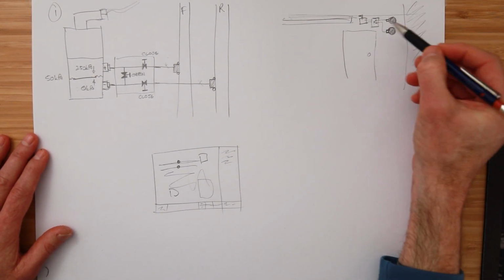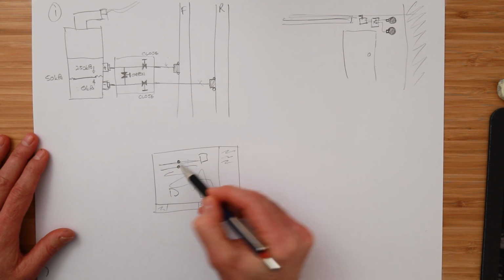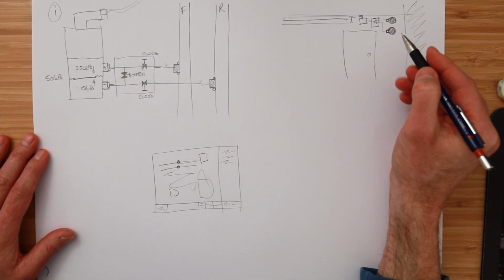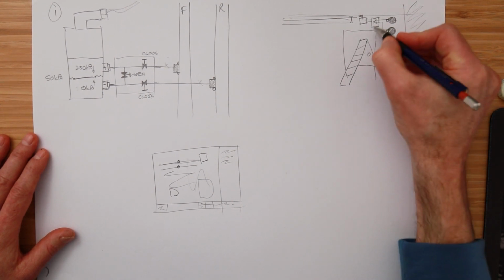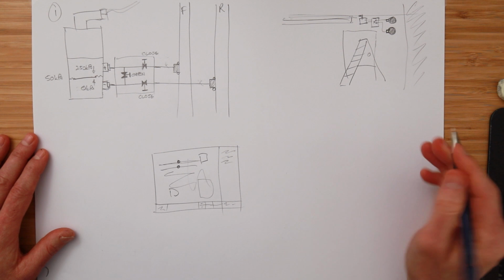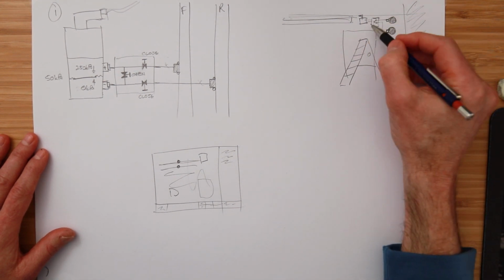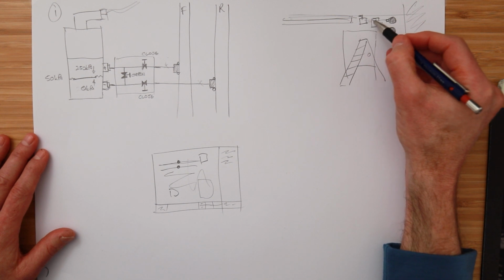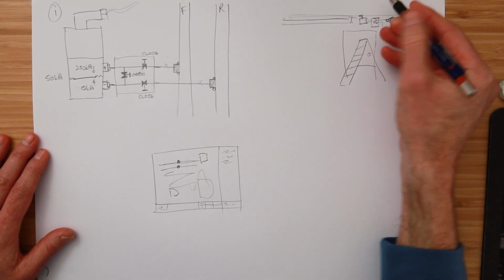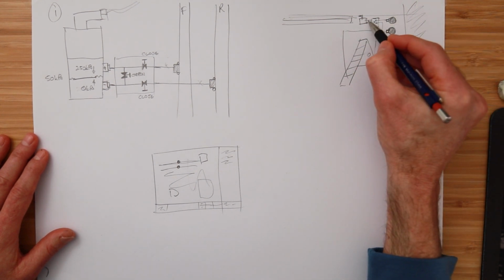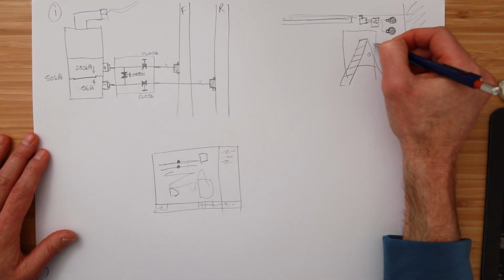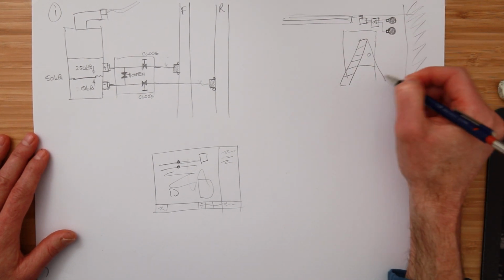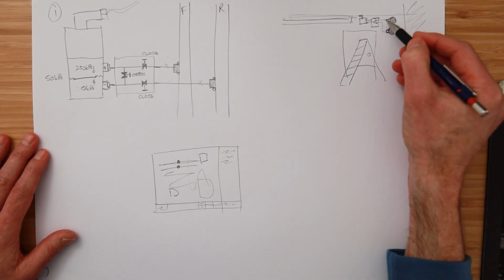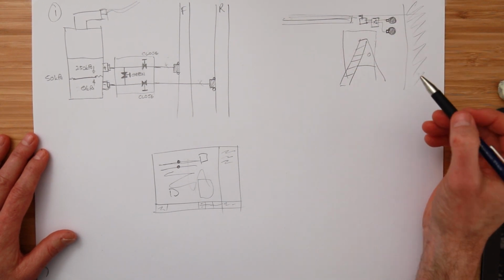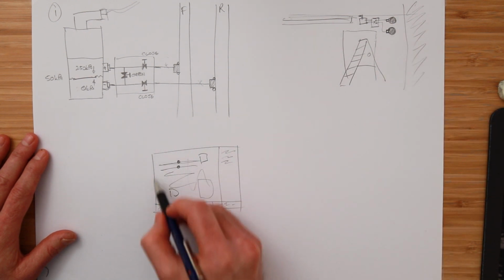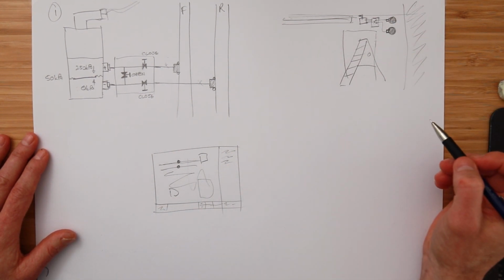Here's the cable. It's a great location from the point of view of good control, but it's above a door here. So the service technician has to get the ladder there and get up to service this pressure transmitter for the next 20 years. Replace it, fix it, check if there's leakages, try and drain the air out of this pipe. This is quite a high location. It's above the pipe maybe, so you can get air in here. So maybe they've got to try and bleed the air out. And then someone opens the door, knocks the ladder over, and there's your buddy lying on the floor with a sore head. So this is a situation where we very easily end up with a sensor in a good location for control, but health and safety wise, it's a very bad location.